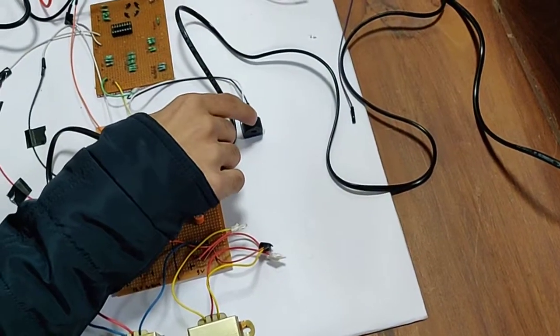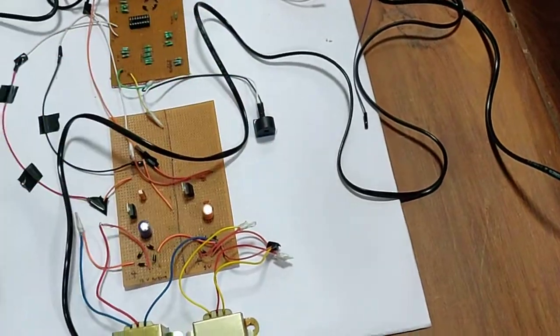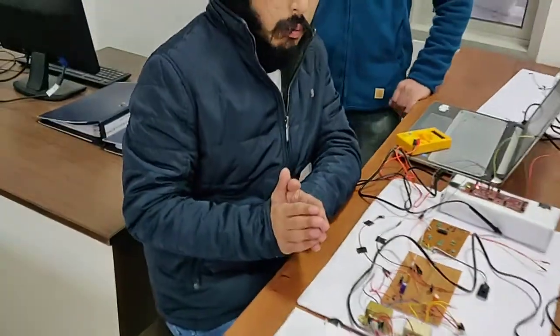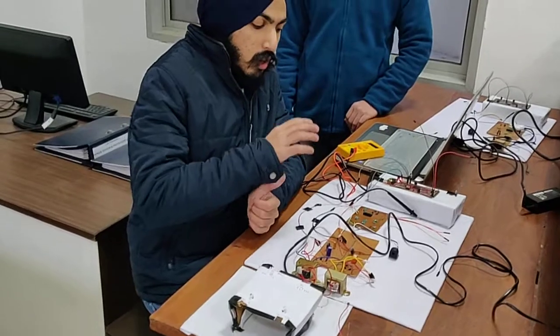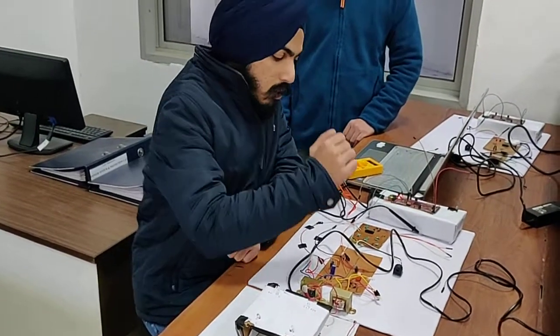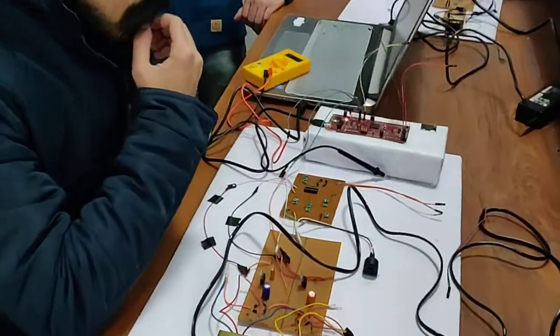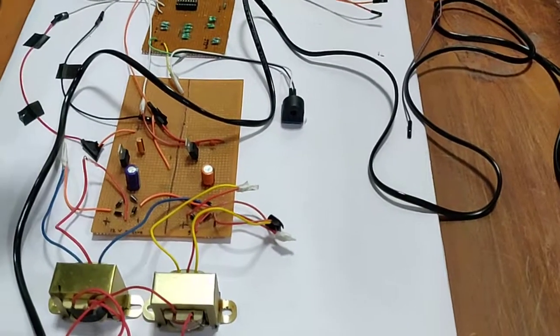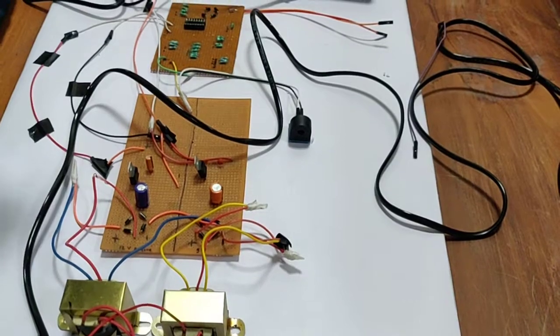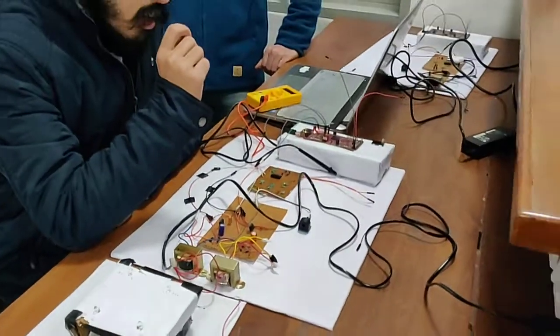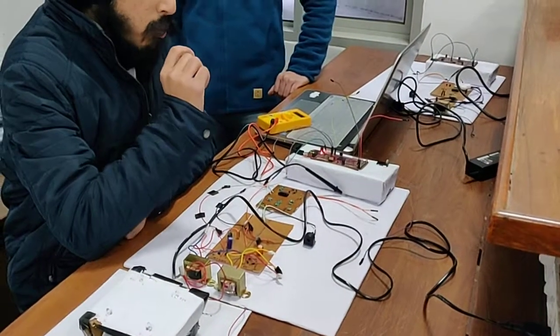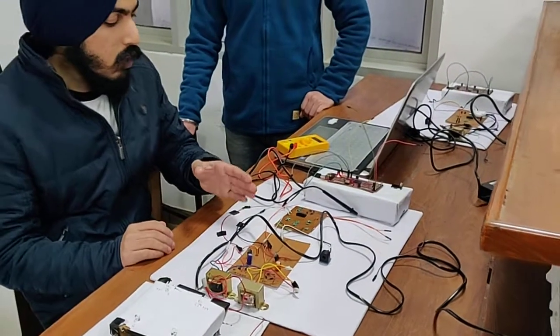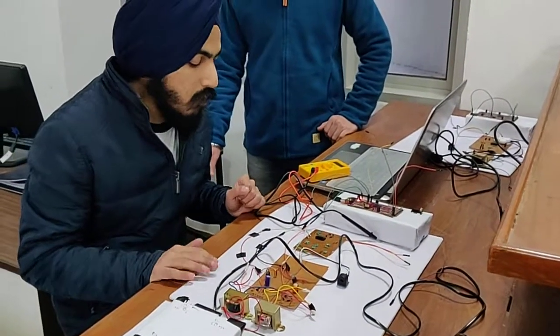Now we are basically constructing an overcurrent relay that will be able to communicate to the central station, which is the server. The current transformer will fetch the current signal. Suppose there is a fault. In case of a fault, there are always higher harmonics and a DC offset. So these need to be removed before the current is given to the numerical relay.